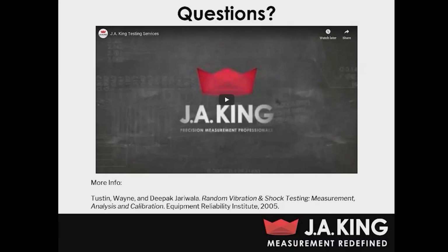Any other questions? Yes. What temperature range can you do vibration at? So we can go up to 170 degrees Celsius, and we can go as low as negative 40 degrees Celsius for both vibration and shock testing.